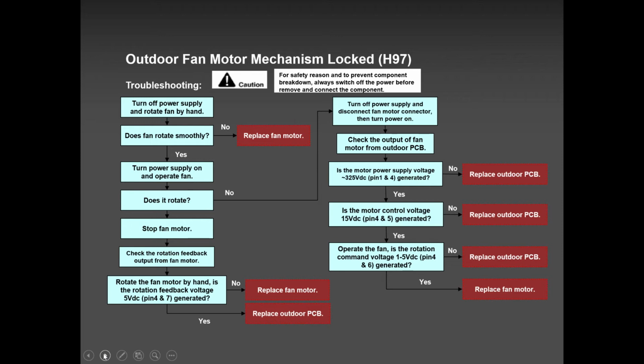And if there is no snow and the fan is nice and free, try and reset the unit. And when you reset the unit and you get an H97 right away, then replace the outdoor fan. One out of 10 calls, honestly, maybe once every 2 or 3 months, I get a call on an H97 where the fan motor took out the outdoor board as well. So that can happen, but very rarely.